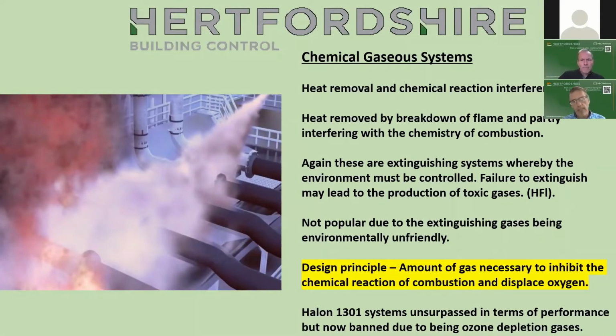hydrogen fluorides developing. And if we do have a chemical gaseous system proposed, the first thing the fire authority wants to know is what it is, because the last thing that anyone wants is the fire authority wandering in. I know they'll probably have breathing apparatus and things like that, but they've got to have an awareness of whatever hazards are being placed in front of them. They tend not to be that popular because the gases are not environmentally friendly. And again, Halon 1301 unsurpassed in terms of performance, but was banned because it was an ozone depleting gas. The design principle is the gas necessary to inhibit the chemical reaction of combustion, and it's obviously to a certain extent going to displace oxygen as well.